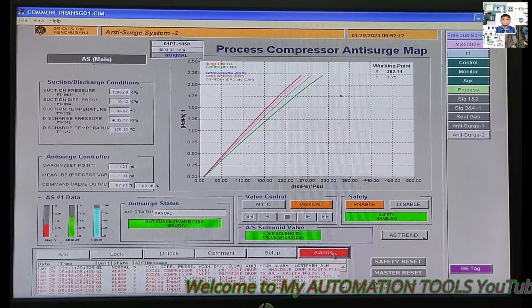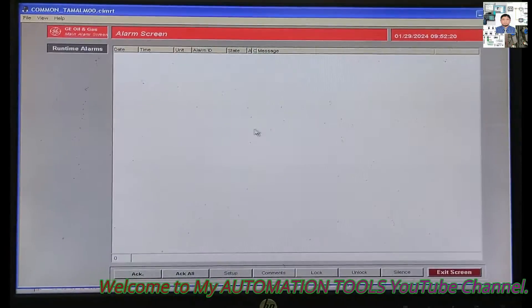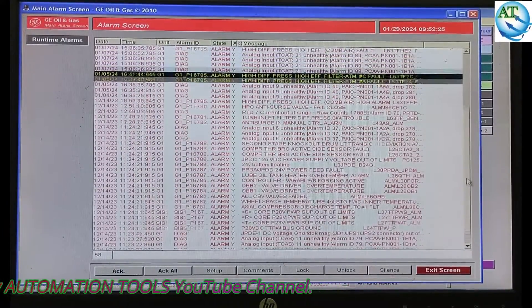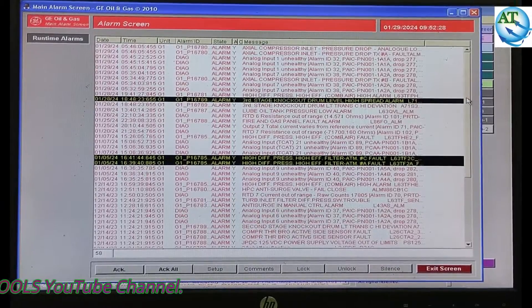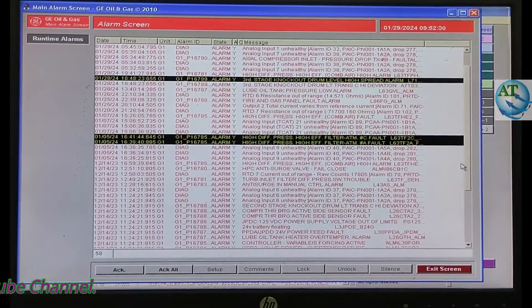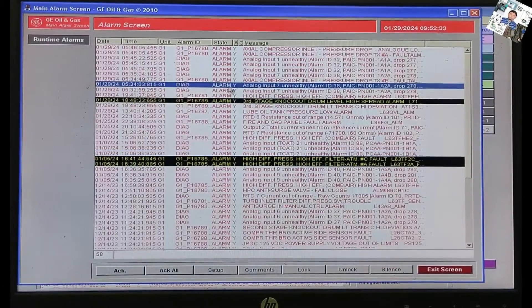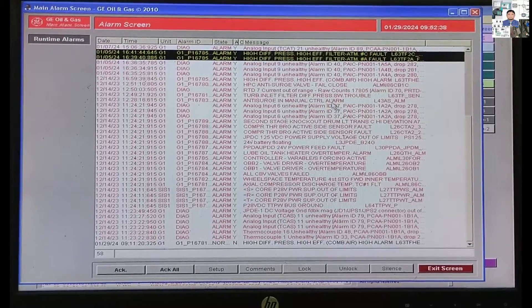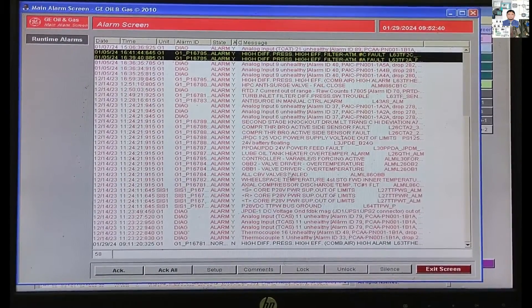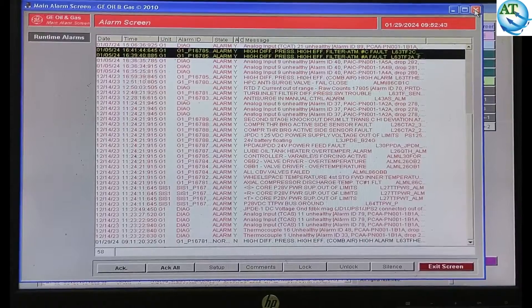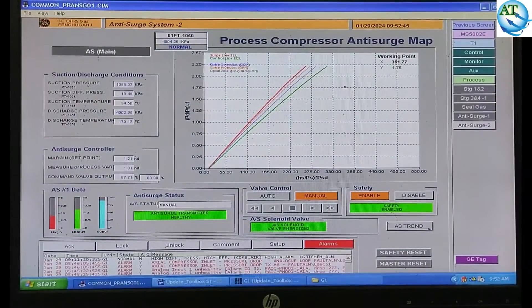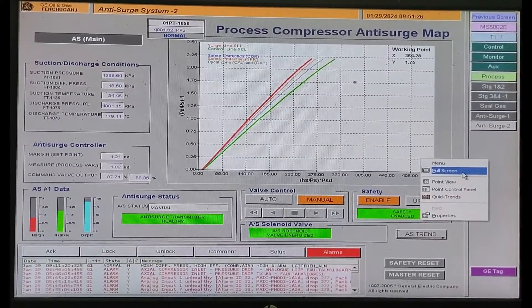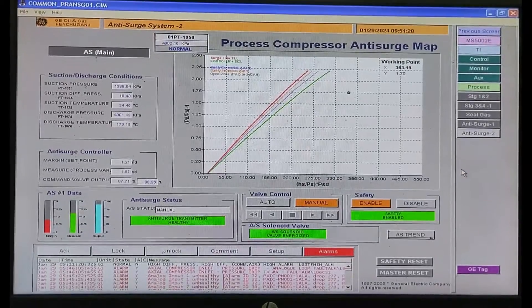We see that when a turbine trips, different types of alarms — a lot of alarms — come in the alarm tab. By seeing these alarms, we become very much confused. Which alarm is the main cause of the turbine TIF? Many alarms come and we cannot understand what is the root cause of the trip of this turbine. We cannot find out the root cause from here. For that reason, we go to the trip analysis recorded data.